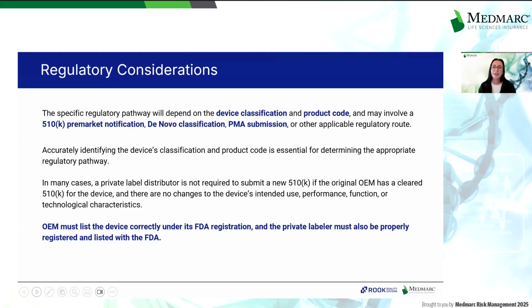807.81(a), a new 510(k) is required if there is a significant modification that could affect the device's safety or effectiveness, such as a substantial change in design, materials, energy source, manufacturing process, or intended use. In such cases, the OEM must update or submit a new 510(k). Additionally, the OEM must list the devices correctly under the FDA registration.